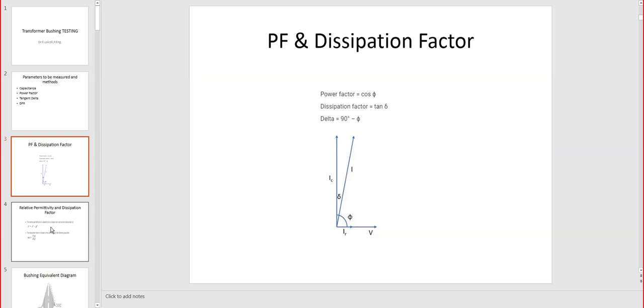So anything that is not at 20 degrees Celsius is actually showing a different value and needs to be corrected back to 20, to compare to the actual rating on the nameplate of the manufacturer of the bushing. So we need the correction, which usually is done automatically by the instrumentation. There are methods to also calculate this if your instrument is not doing it and is an older type.